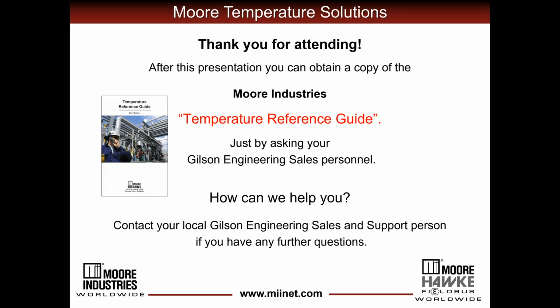Question from Daniel. What's the typical error added by D to A and A to D conversion? Well, that depends on the device, and they usually specify that on the devices, okay? It is small, but when added up 2 times, it adds up. If you take a look at our specs, you'll find that stability figures are based on 1 year, 3 years, and 5 years. And they go from 0.08% of span to, in 5 years, 0.18% of span. The conversion error is small, but when added 2 times, that is conversion from analog to digital to analog, and then analog back to digital, it is additive. I don't have a spec in front of me. It depends on the device.